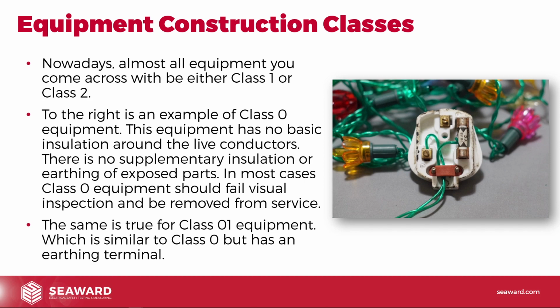Similar with Class 01 equipment. Class 01 is Class 0 equipment, but it does have an earth terminal. So sometimes you imagine an old brass lamp or something like that with a 2-core flex going to it, but there's an earth terminal. So if somebody wanted to, they could connect an earth wire to the metal parts, but that's not earthing as part of the plug. That's just somebody could put an earth to it if they wanted to. So generally, in most normal environments, Class 0 or Class 01 equipment is failed on site.